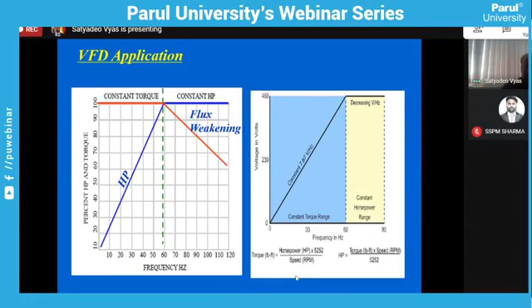So there are two modes of operation. One is the constant torque mode. Up to base speed, you can go in the constant torque mode. Beyond that, as the speed is increasing, your flux is decreasing, so torque is decreasing. Torque is decreasing in the same proportion as frequency is increasing. So P is equal to 2 pi N T. N is increasing, T is decreasing. You are running this motor in the constant power mode, that is the constant HP mode. There are two modes of operation.